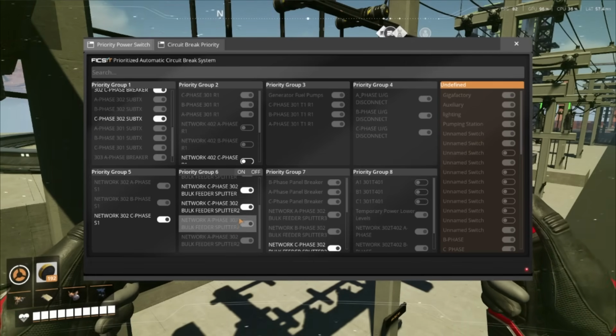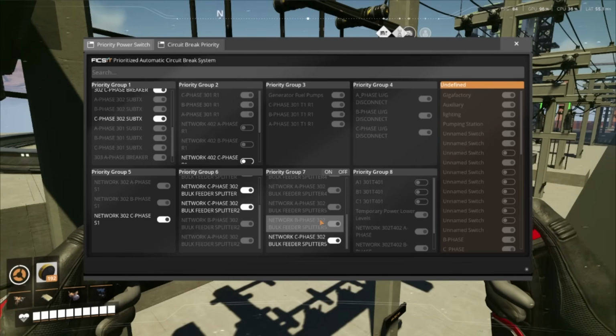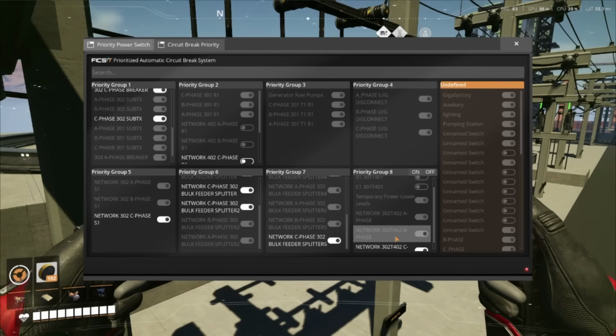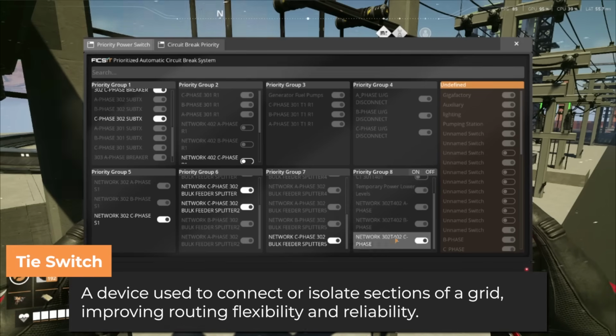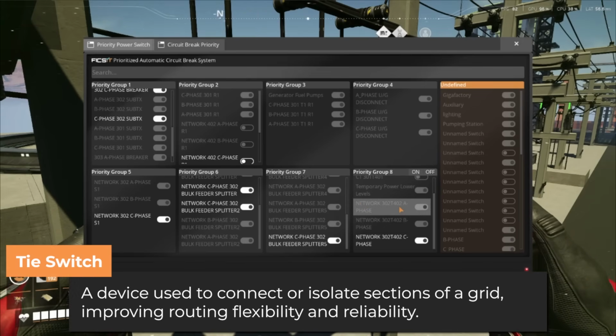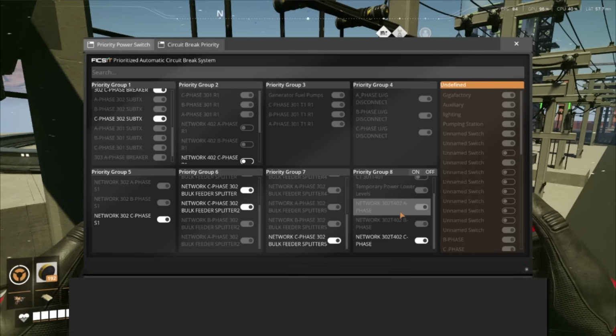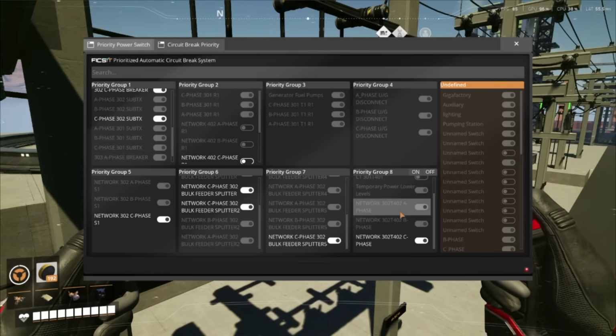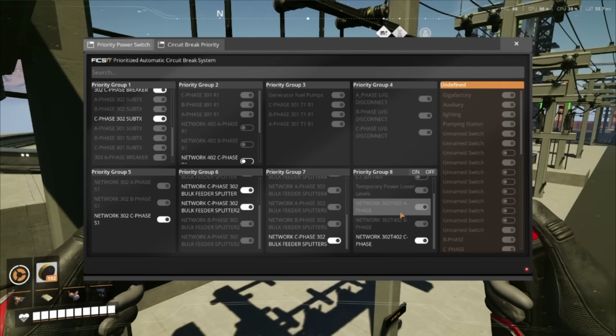Hopefully at this point you know how to use priority power switches. But for the purpose of what I'm explaining here, your tie switches are going to be lowest priority, because they're going to be open most of the time anyway. In the event that you do close them, you want to make sure your load is going to be lower than your generation capacity or your capacitor capacity.